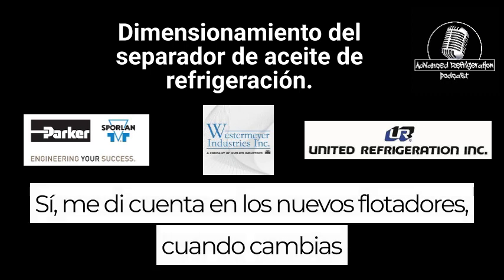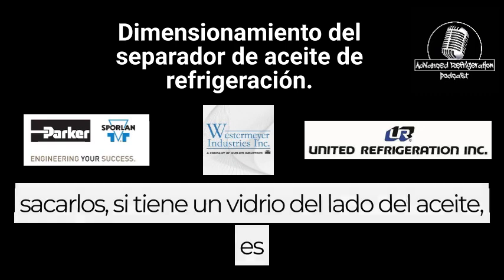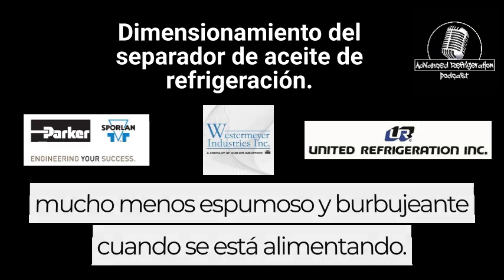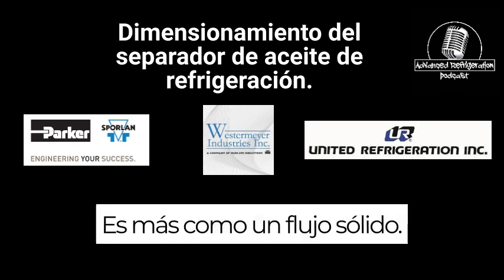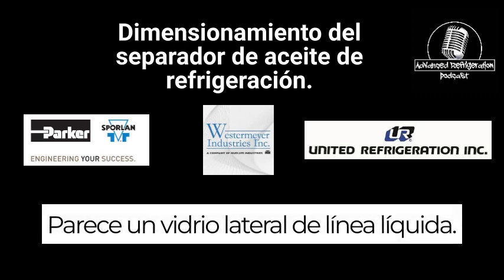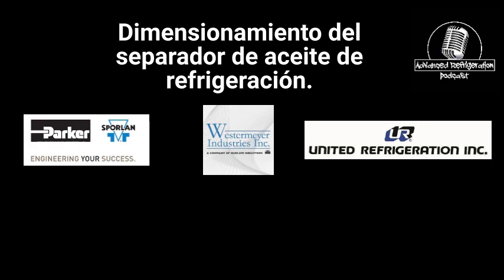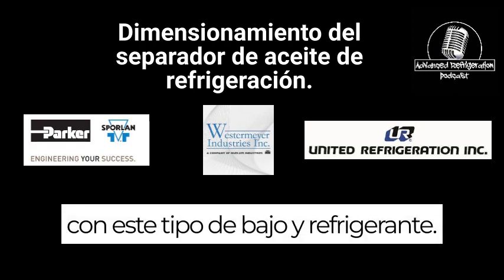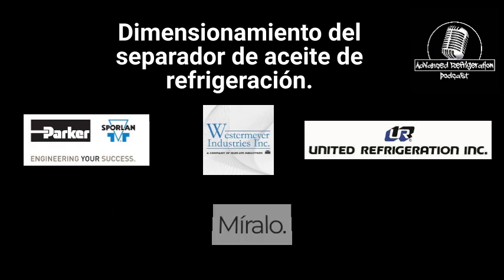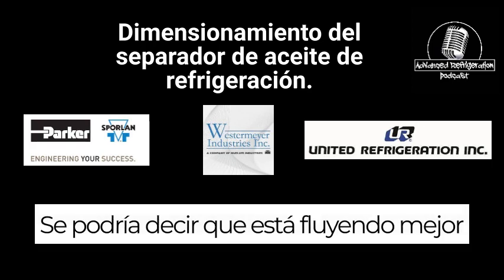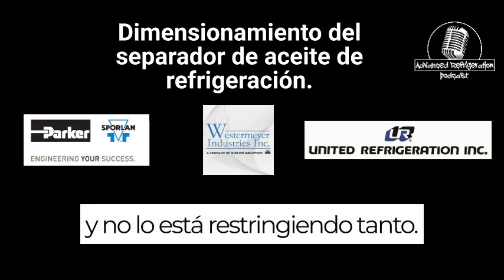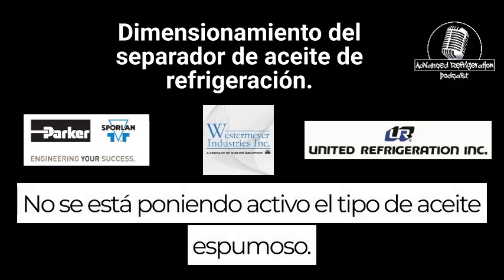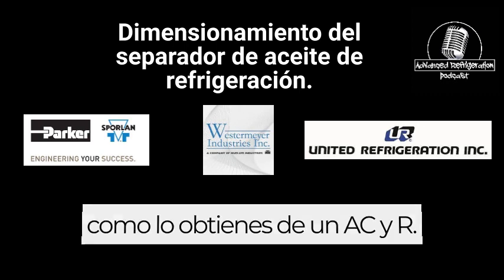Yeah, I noticed on the new floats, when you change them out, if you have an oil sight glass, it's a lot less foamy and bubbly. When it is feeding, it's more like a solid flow. It looks like a liquid line sight glass, versus when it's low on refrigerant. It has a lot better flow look to it. So you can tell it is flowing better and not restricting as much. And it's not getting that foamy type of oil like you get from an AC and R.